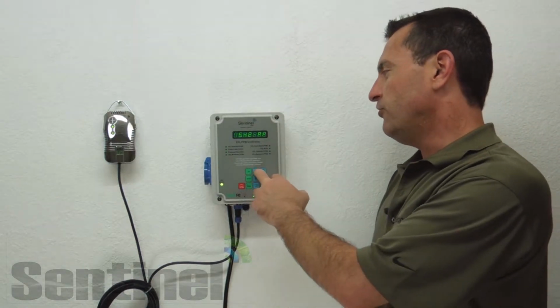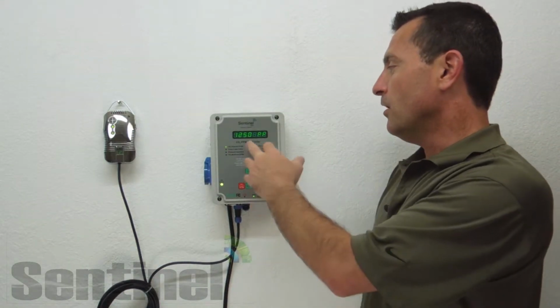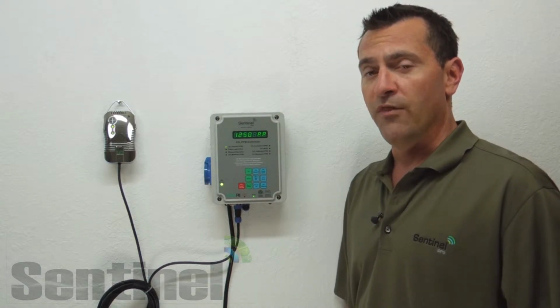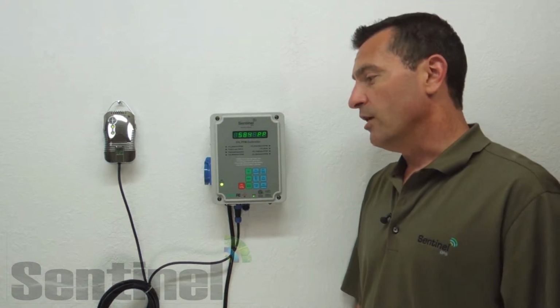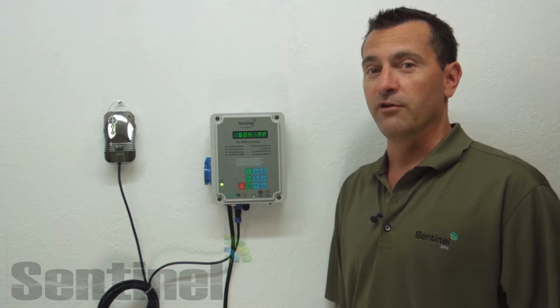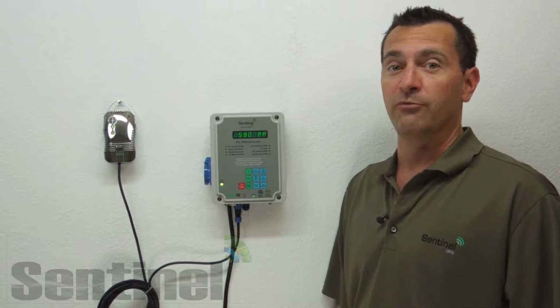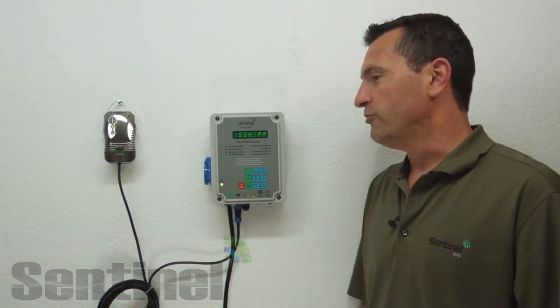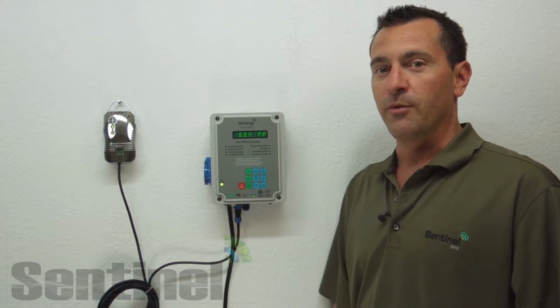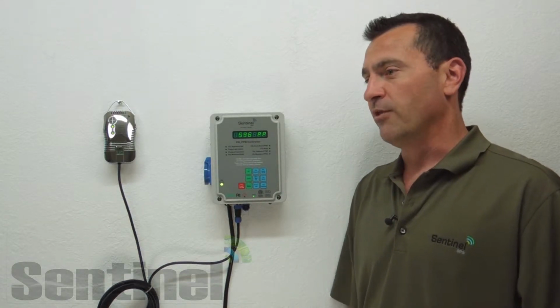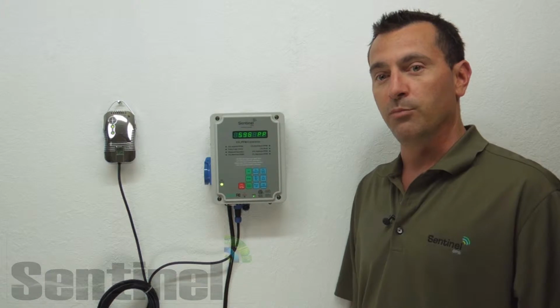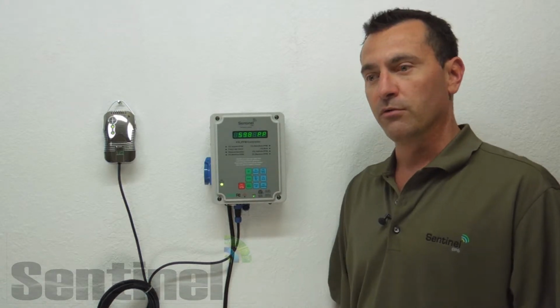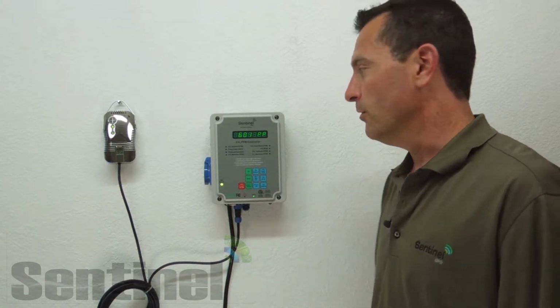It goes on there. The CO2 set point is the next item you would look at. It comes set from the factory at 1,250. Common levels you'll see in indoor gardening are 750 parts per million up to 2,000 parts per million. Most research says once you get to about 1,500, that's about the maximum you need. So that's what we recommend to people. You waste less CO2, and there's less chance to have a buildup in your room.